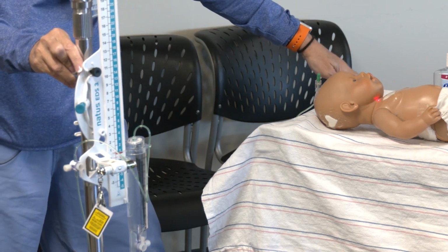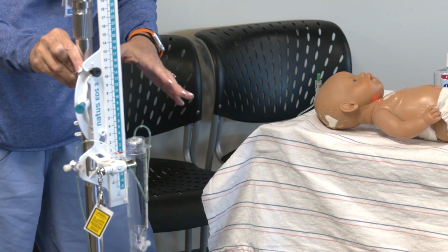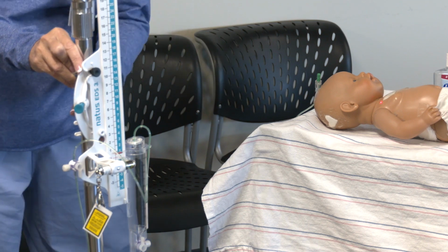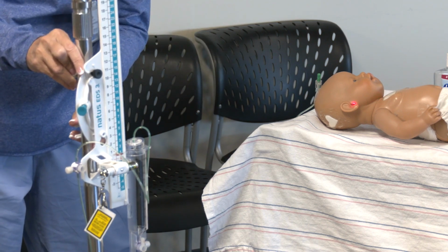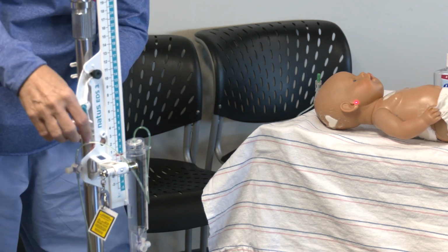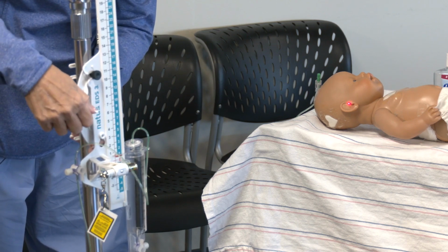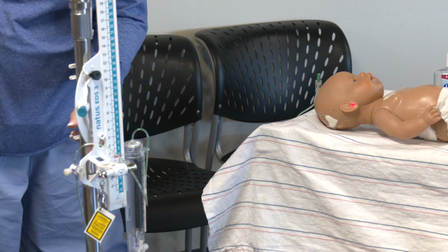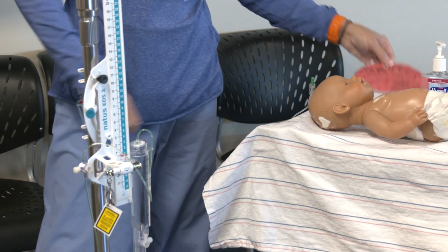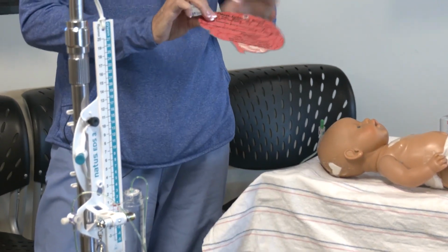It could be a different order where they're zeroing to, so you just would point the light to whatever your order is. On EVDs and subdural drains, it's almost always the tragus. So it's right there. I'm going to secure this there with the green screw. Okay, and now we've zeroed to the tragus. So we've got it covered as far as leveling and zeroing to the tragus now.